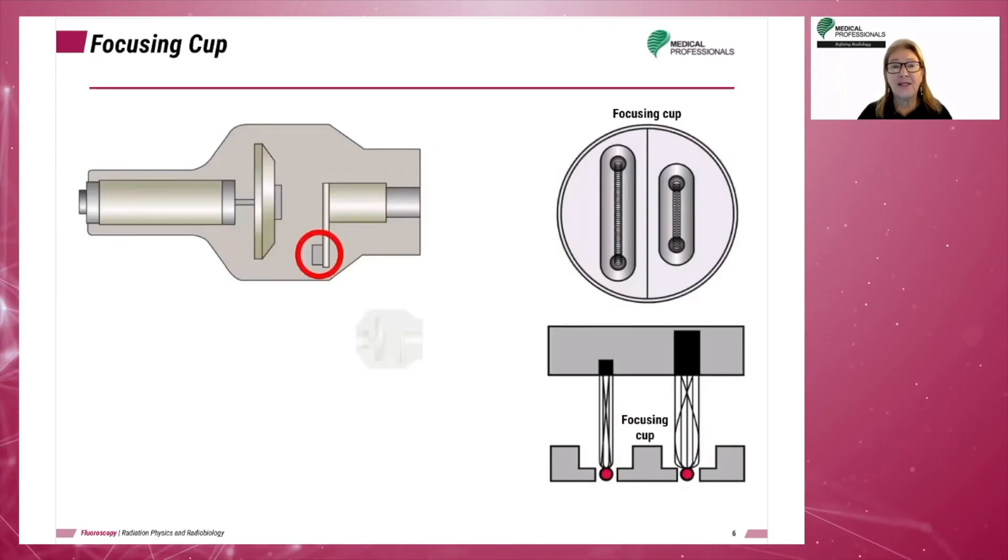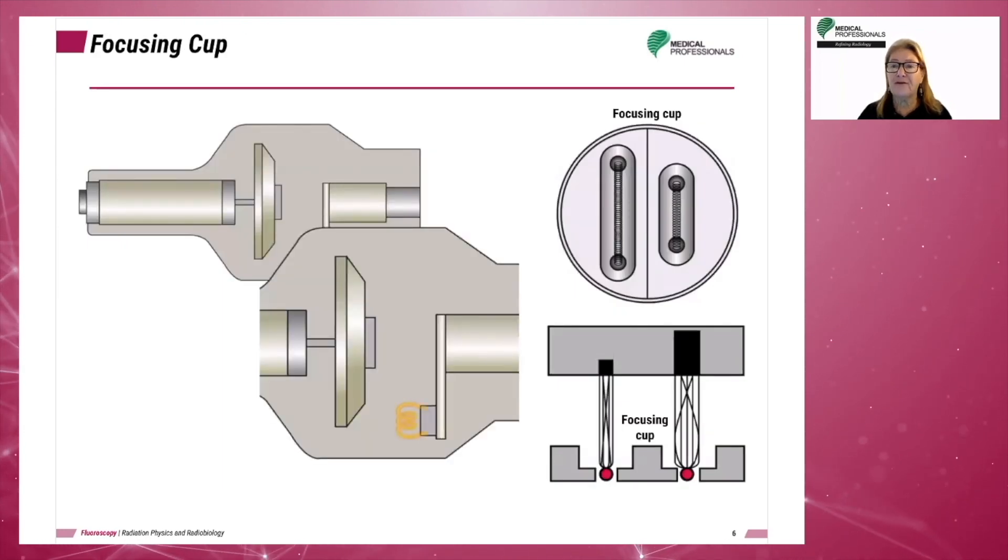The device used to keep the electrons close to the filament in the cathode is called a focusing cup. If the focusing cup was not present, the electrons would float freely within the tube. This would not be efficient for X-ray production because it would be difficult to control the number of electrons present for radiation production.